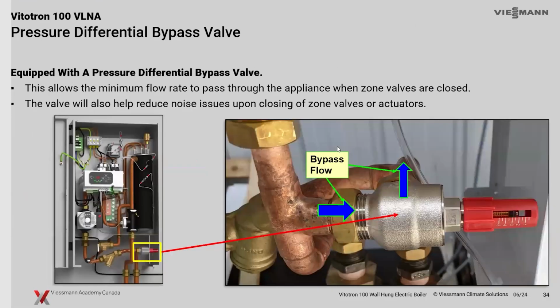And of course, we've also added in a little differential pressure bypass valve as well. Something that we use a lot when we're talking about unloading pump head if you're not using a variable speed pump, and of course this is a 3-speed pump we have built into this little unit. During your commissioning of your system, of course, you're going to set this to make sure that we meet the flow rate that we're looking for. So it's built in. Again, you don't have to buy this. It's already part of the system.